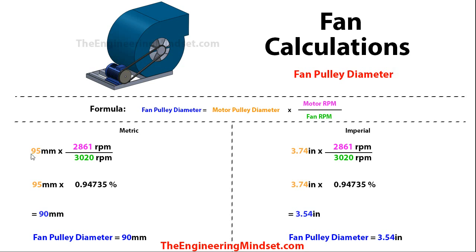So for the first calculation, we've got a 95 millimeter diameter pulley on the motor — that's 95 millimeters across, or 3.74 inches. And we know that the motor is going to be rotating at 2,861 RPM, same for the imperial. And then the fan, in order to achieve the airflow rate that we need, it's going to be rotating at 3,020 RPM, same for the imperial. If we do the division first, we get 0.94735 — it's a ratio since we're dividing the same units. So 95 millimeters multiplied by that ratio equals 90 millimeters, or 3.54 inches. So the fan pulley diameter needs to be 90 millimeters in order to achieve the design.